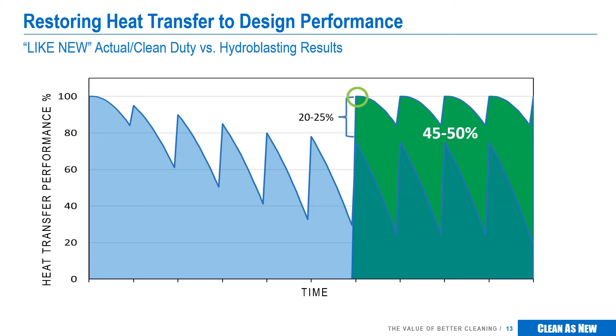In this example, we are showing that the bundle is cleaned at a regular interval. For most bundles, hydroblasting alone can never get the bundle back to 100%, so over several successive cleanings, the restart performance continues to degrade. Clean as New solves this problem. Our approach allows the bundle to be returned to service at 100% of design capacity. In this particular fouling model, because of the difference in the shapes of the two curves, a 20 to 25% improvement in return to service performance results in a 45 to 50% performance improvement over the next interval.